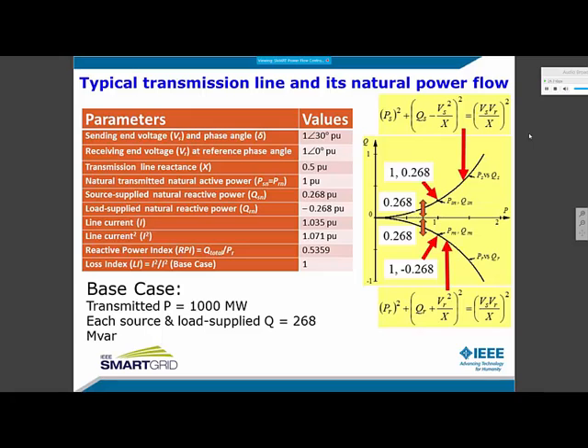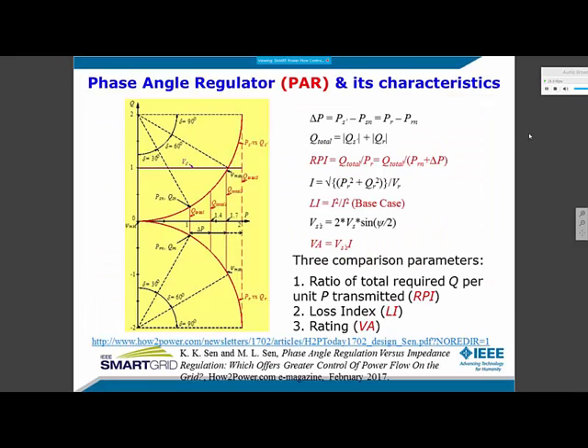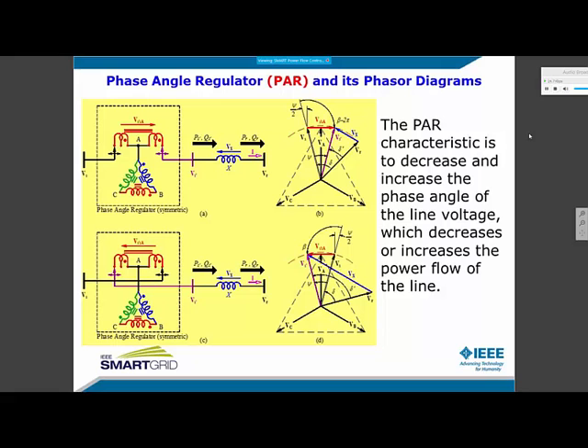Now, to compare various power flow control methods on the same terms, let's define three metric parameters. Those are called the reactive power index, the loss index, and the rating. The reactive power index is defined by the ratio of total required reactive power per unit real power transmitted. Loss index is the ratio of the current squared with respect to the current squared of the base current, and the rating is the rating of the equipment. All three parameters cost money. Therefore, the lower the values, the better it is. More information you can find at this reference.